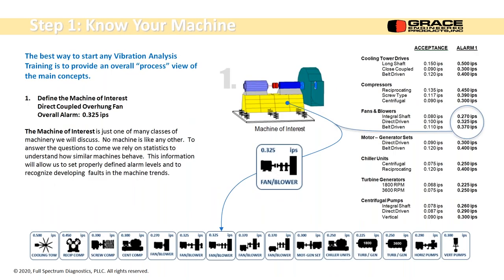Okay. First of all, the best thing to do is to know your machine. So the machine I have shown here is a direct-driven overhung fan application. It's on isolators, and there's a machine base under that. That's not much more information, but this is a class of machinery. On the right here are the acceptance levels and alarm levels for 7 different classes of machinery. And there's like 18 different machine types involved in this.